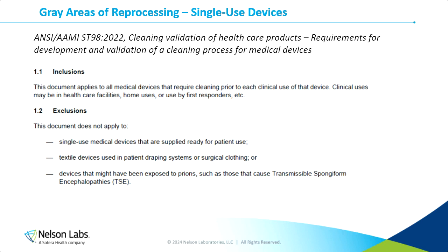So this is an excerpt from the scope section of AAMI ST98. And in the inclusions, you can see that this document applies to all devices that require cleaning prior to each clinical use of that device. Now, it doesn't necessarily explicitly state single-use devices that are supplied non-sterile, but I would say that it implies that these sorts of devices are within scope of this document.